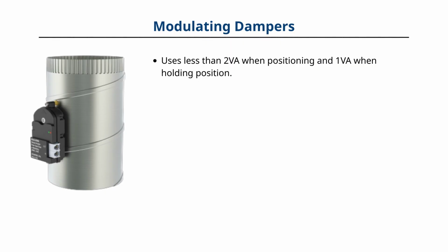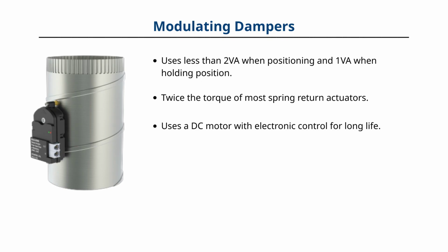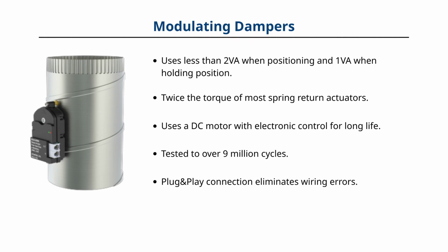The damper actuator uses less than 2 VA when positioning and 1 VA when holding position and has twice the torque of most spring return actuators. The actuator uses a DC motor with electronic control for long life and has been tested to over 9 million cycles. Plug-and-play connection eliminates wiring errors.